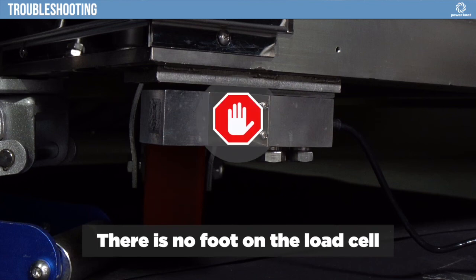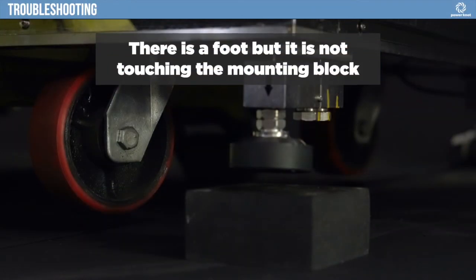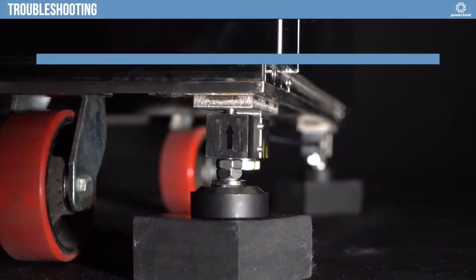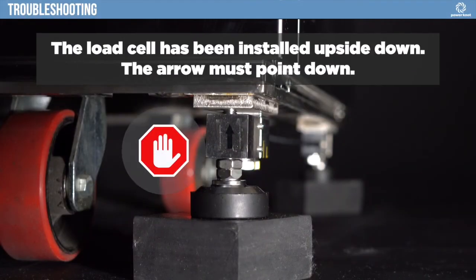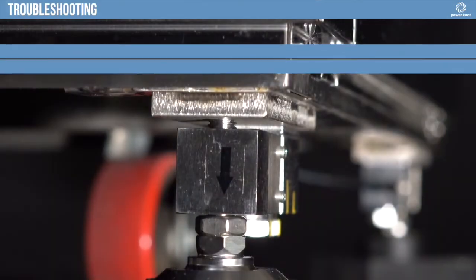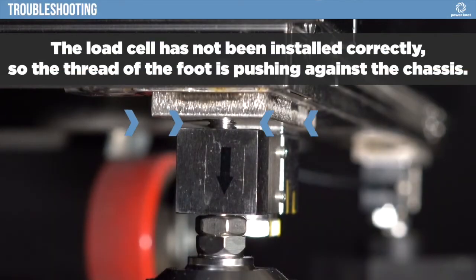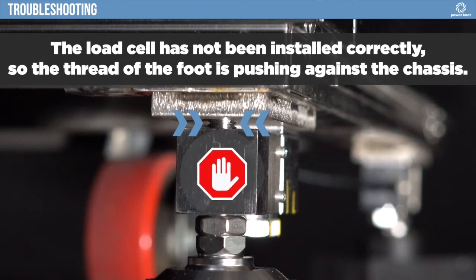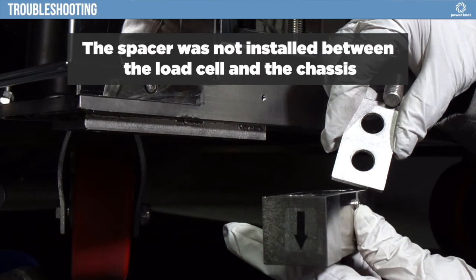If the load cell you just installed reads 0 or another error, check the following. There is no foot on the load cell. There is a foot, but it is not touching the mounting block. The load cell has been installed upside down. The arrow must point down. The load cell has not been installed correctly, so the thread of the foot is pushing against the chassis. The spacer was not installed between the load cell and the chassis.